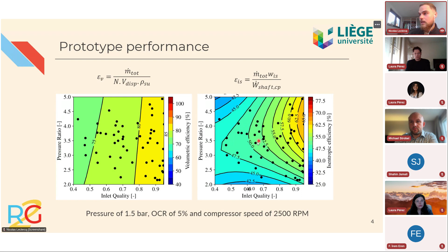Two-phase compression creates irreversibilities due to the temperature difference between the two phases. When you compress a two-phase fluid, the vapor phase is going to increase its temperature, because when you compress vapor the temperature usually rises, while the liquid phase is incompressible, so normally it's not going to change. So you have heat transfer between the two phases, and the higher the temperature difference between them, the lower the resulting efficiency. And due to the liquid, the leakage gaps of the machine can be increased, and this is why you have this reduction of volumetric efficiency. My theory is that the tip seal of the machine is moving due to the liquid, and that's why we have a lower efficiency on that side.